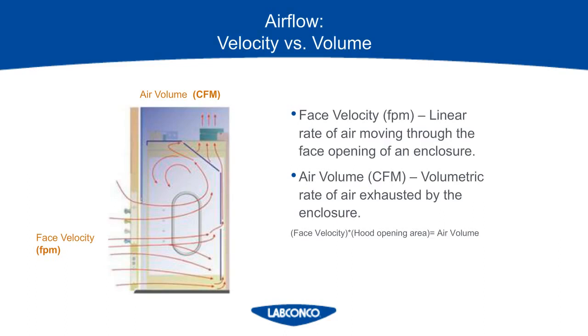You'll see most of today's fume hoods published with an operating range of 60 to 100 feet per minute. Sometimes they cannot be operated as low as 60 feet per minute, and we'll get into that later during the high-performance hood discussion. Just pay attention to manufacturer's published data to see what range is acceptable. Now we know what the important air measurements are on a fume hood, but there are different types of mechanical systems we can put the hood on, so we're going to take a quick look at those now.